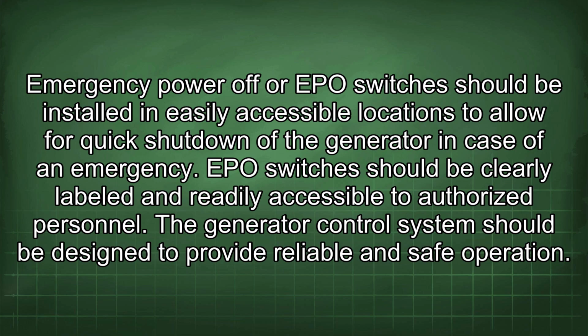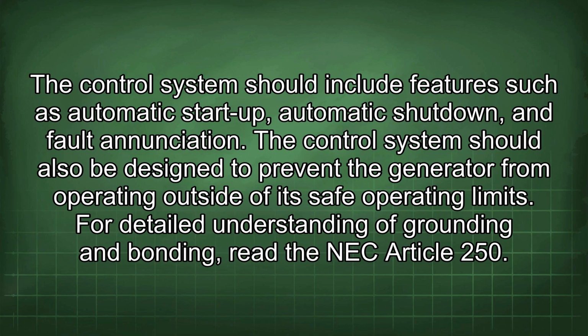The generator control system should be designed to provide reliable and safe operation. The control system should include features such as automatic startup, automatic shutdown, and fault annunciation. The control system should also be designed to prevent the generator from operating outside of its safe operating limit.